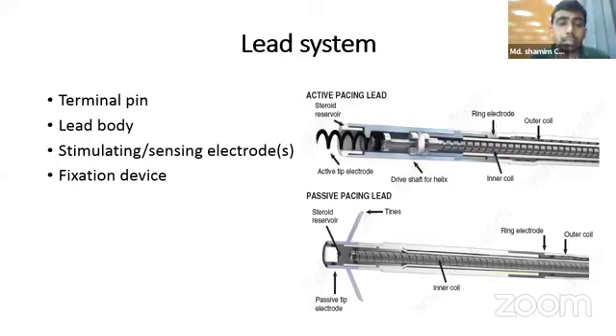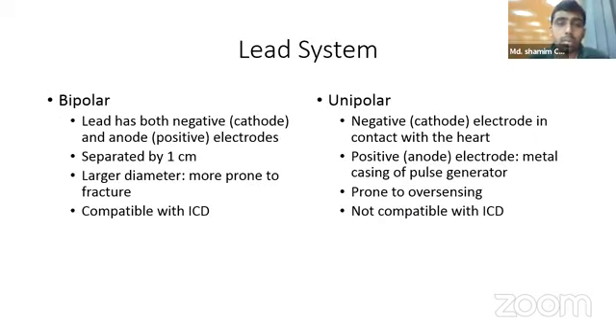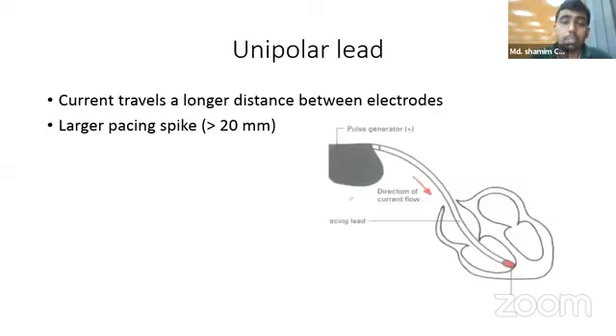Regarding the lead system, it has 4 parts: terminal pin, lead body, stimulating and sensing electrode, and fixation device. The lead system usually are 2 types, bipolar and unipolar. Bipolar leads have both negative and positive electrodes within the heart separated by 1 centimeter. It has larger diameter and is more prone to fracture, compatible with the ICD. And the unipolar leads are those in which the negative electrode is in contact with the heart, but the positive electrode is within the pulse generator. It is prone to more oversensing, but not compatible with the ICD.